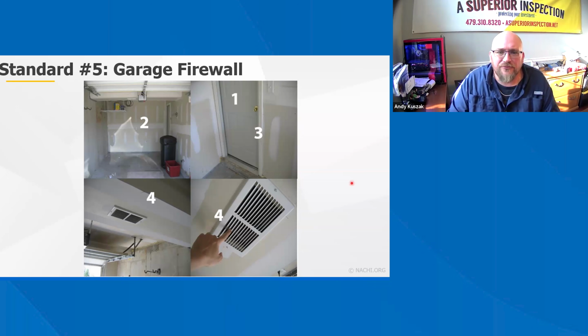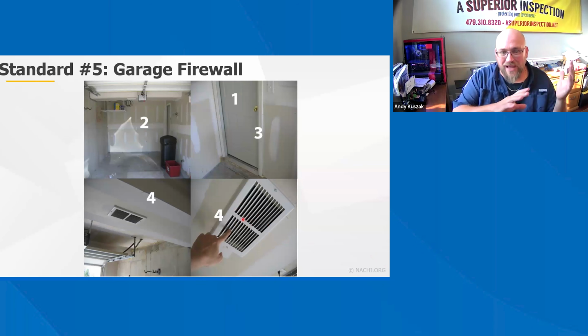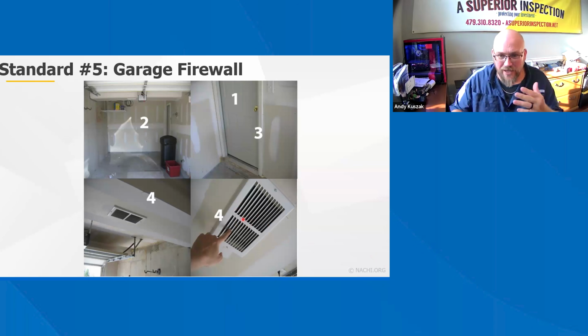All right. Number four. Where an air duct passes through the drywall located on the garage side of the firewall separation, the duct material should be a minimum of number 26 gauge sheet material. There should not be any openings in the ductwork within the garage area. So this is kind of a little deceiving. A lot of times you're going to have ductwork that will pass through the garage, and that is okay. But having an opening like the register that we see in number 4 is not acceptable.